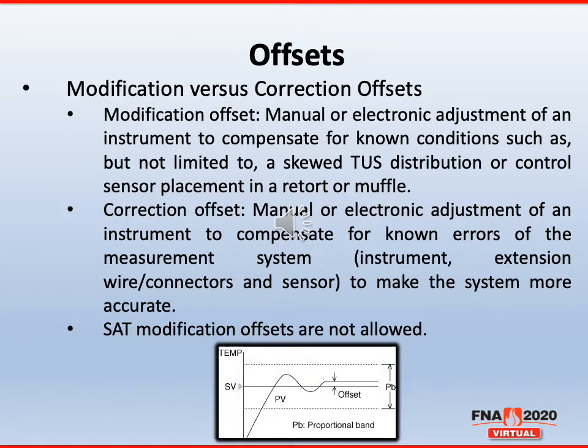One of the places that we believe that we made some great strides in AMS 2750F is putting some more meat and potatoes behind the use of offsets. Again, one of those items in the specification that has caused a lot of problems of how to document what type of offset is allowable or not. So the group decided that we'd make two different offsets. We call them a modification offset versus a correction offset.